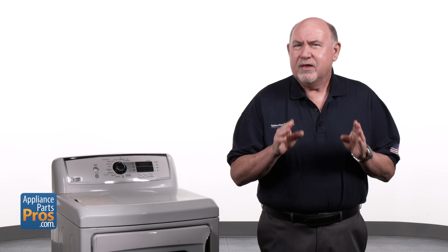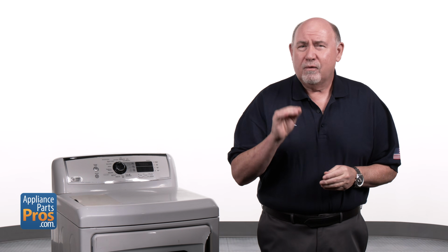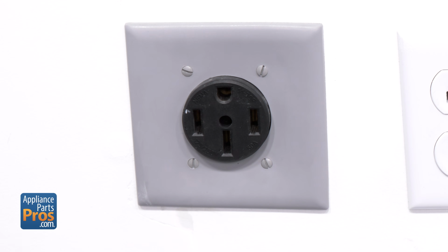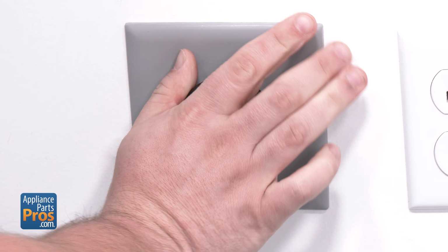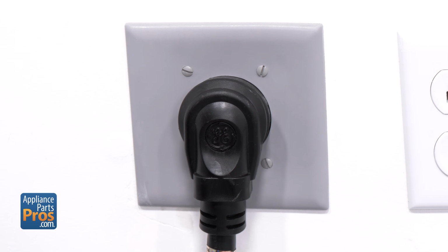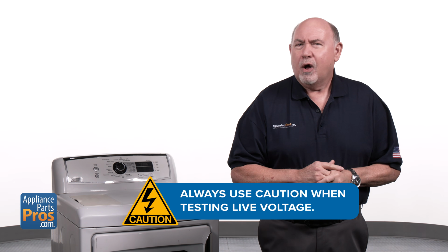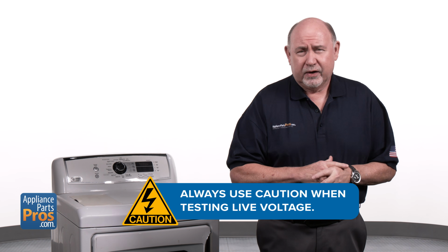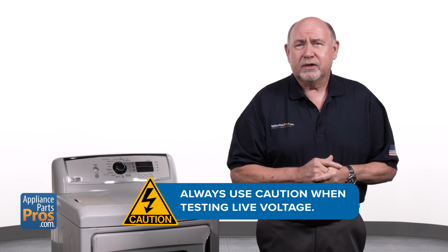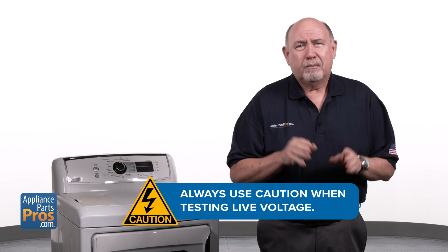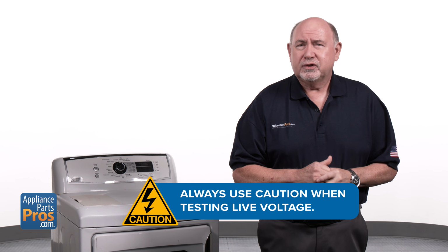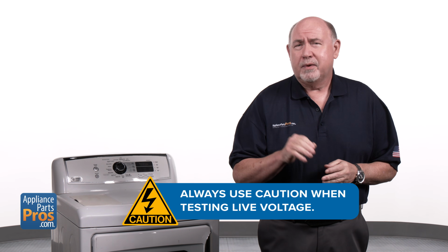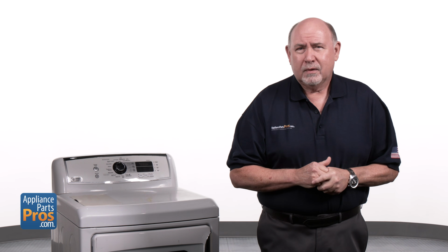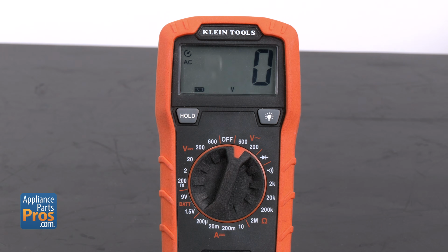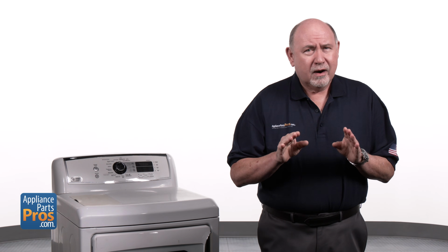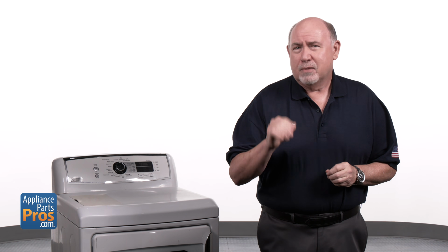Now, before we do anything else, power stays on for this test. We'll be checking the voltage with the dryer running, so stay focused and be safe. Extreme care should always be taken to protect against electric shock, which could potentially result in serious injury. Please do not test live voltage if you are uncomfortable using a multimeter around live voltage. Set your multimeter to volts AC. Start the dryer and make sure it's in high heat mode.